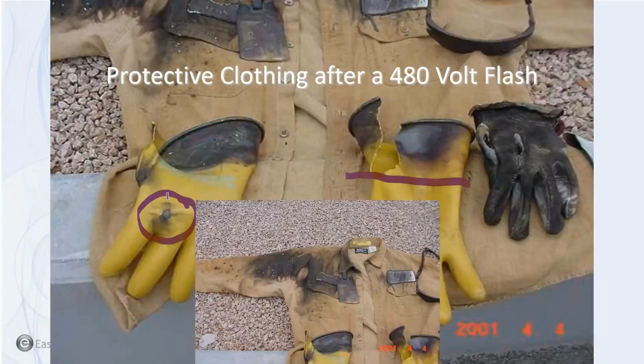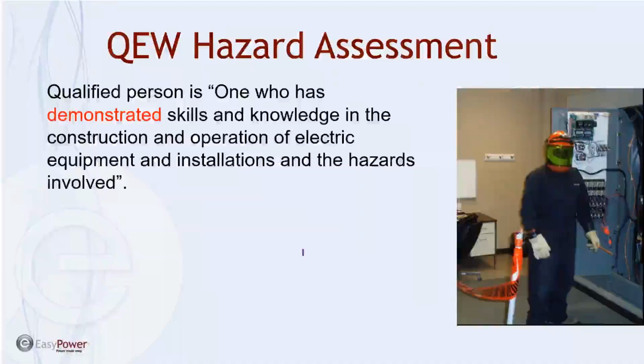So you can see this person was standing to the side, and they ended up with a burn on their shirt. It held up for the most part. It did breach a little bit in this area right here. So that's why it's estimated to be over 10 calories on this 8.4 calorie shirt.